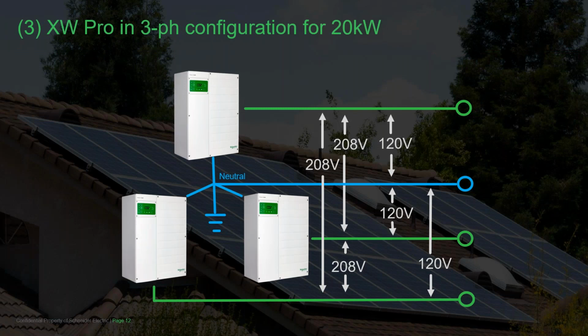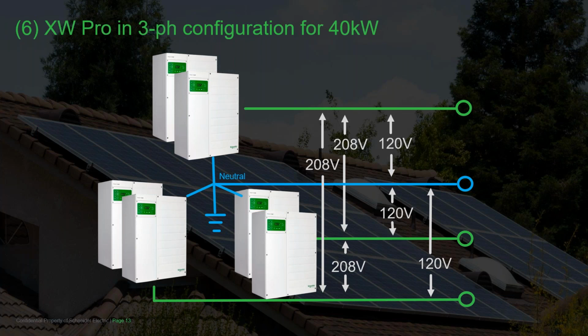For a three-phase system, XW Pro requires 1 or 2 inverters per phase. A 3-inverter system supplies a nominal 20 kW, while a 6-inverter system provides 40 kW. Be aware that 2 XW Pro units cannot recognize 2 lines of a 3-phase source. The 3-phase XW Pro system will have a common neutral. From line to line, you have 208 volts. From each line to neutral, you have 120 volts. Here's a 40 kW system represented. A 6-inverter system will require 2 power distribution panels. More on how everything ties together later in this presentation.